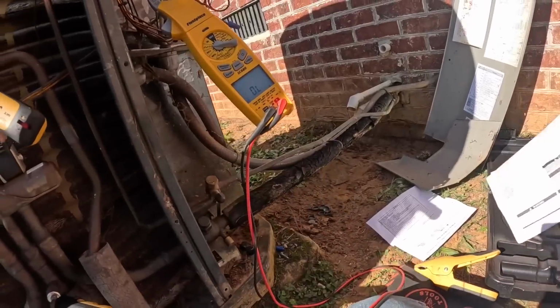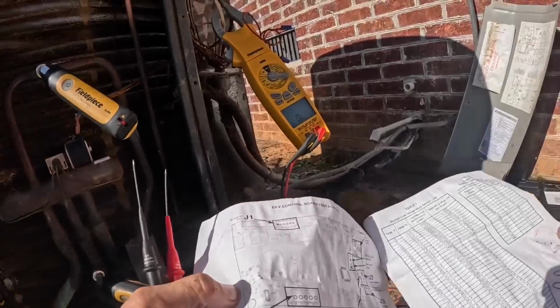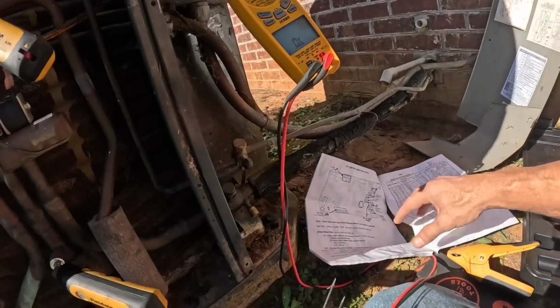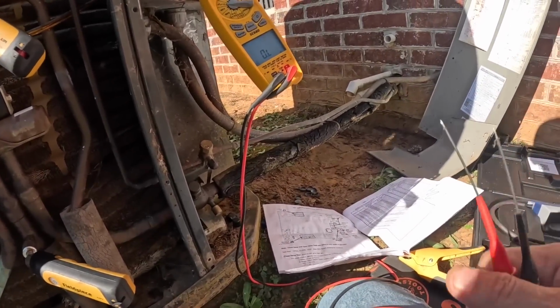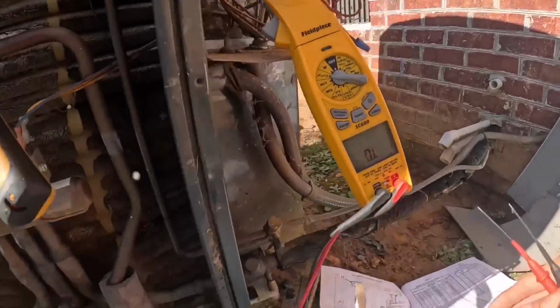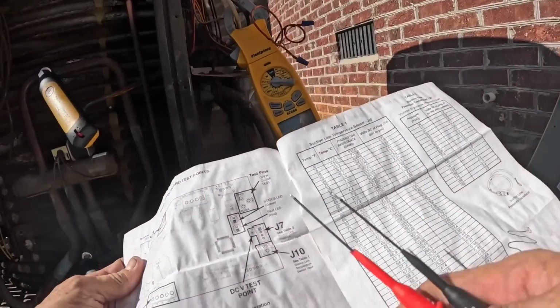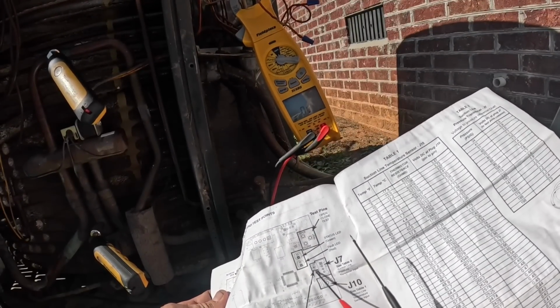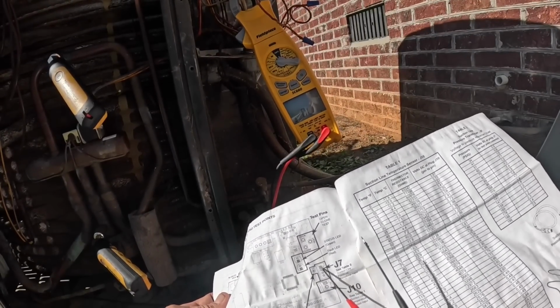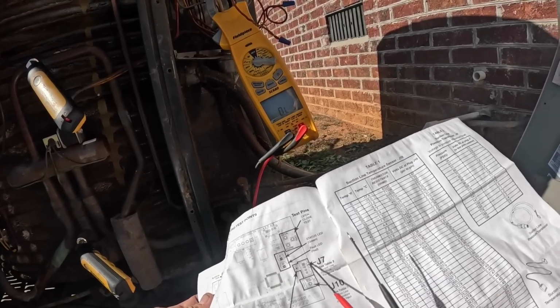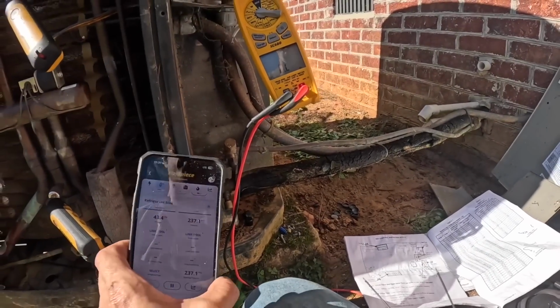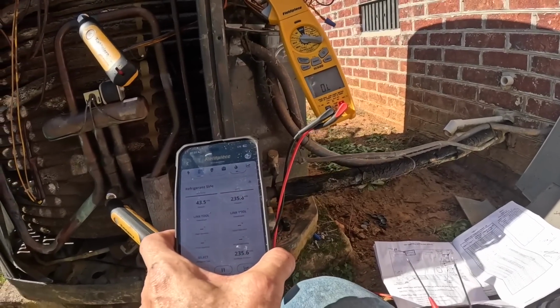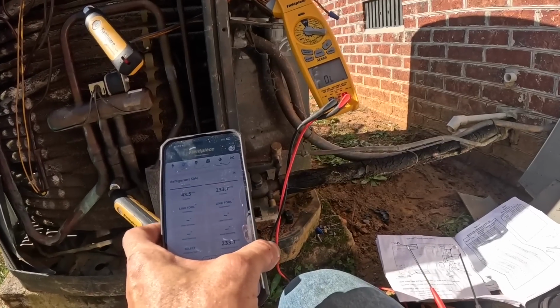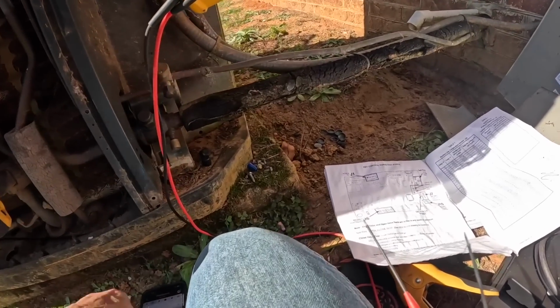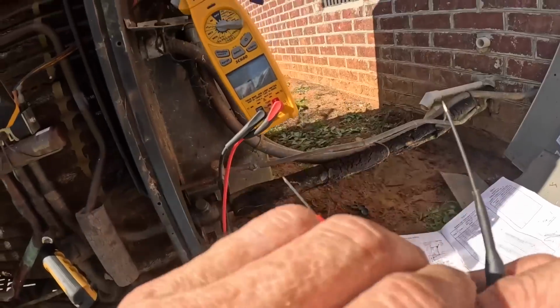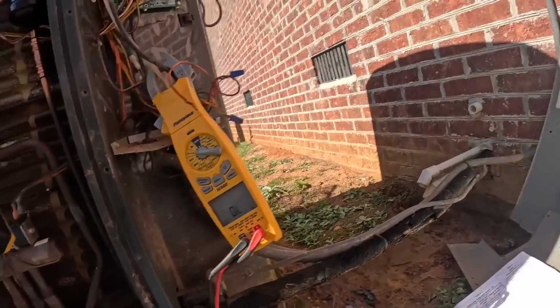Let's try to test those voltages again. I honestly don't know, I'm beginning to think that pressure transducer is my problem. If y'all look here, it says to test right here at VP plus, and then test this top pin. And right now my suction pressure, and that's on true suction, is 43.5. So I should be at something like 1 volt DC.